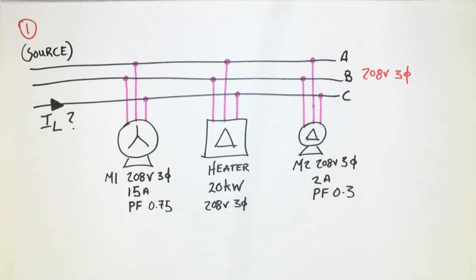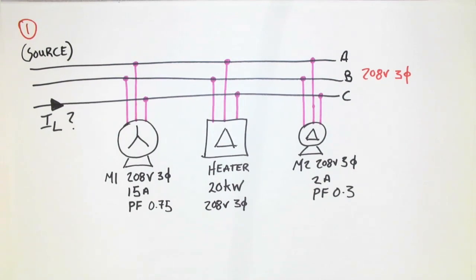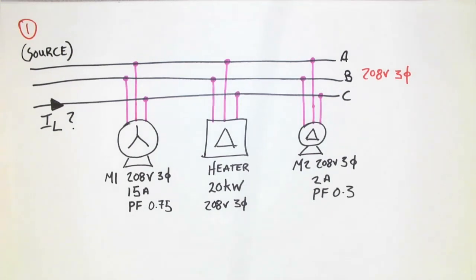Motor one has a power factor of 0.75, whereas the heater is operating at a power factor of one and is 20 kilowatts worth of power, 208-volt three-phase. Motor two is also 208-volt three-phase, 2 amps — that would be the line value — with a power factor of 0.3.